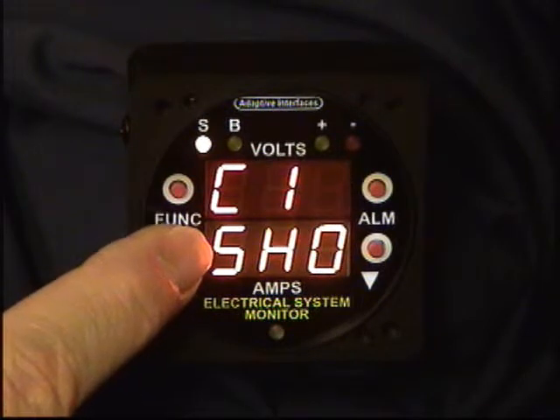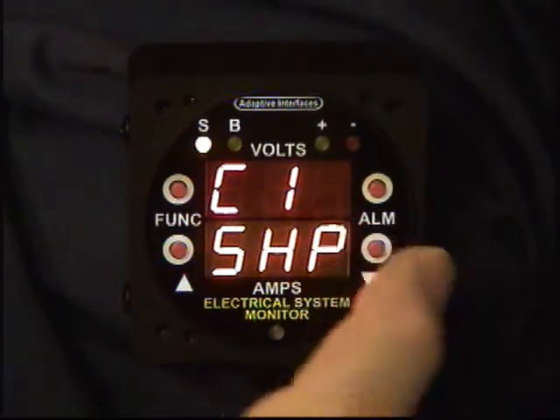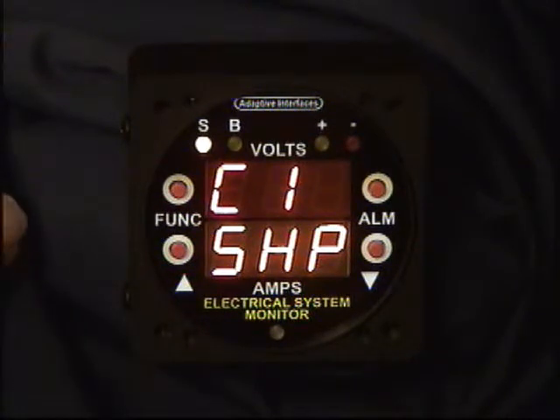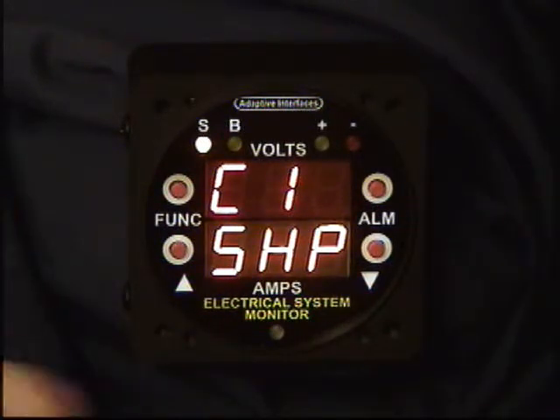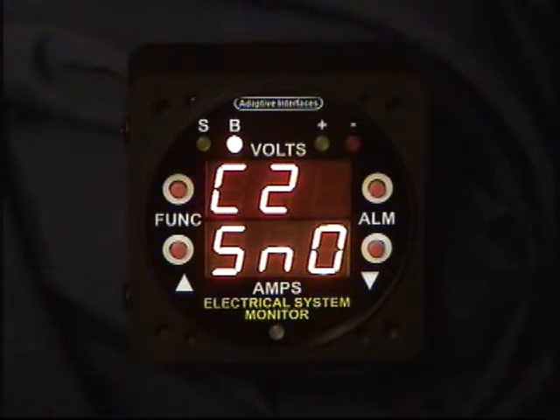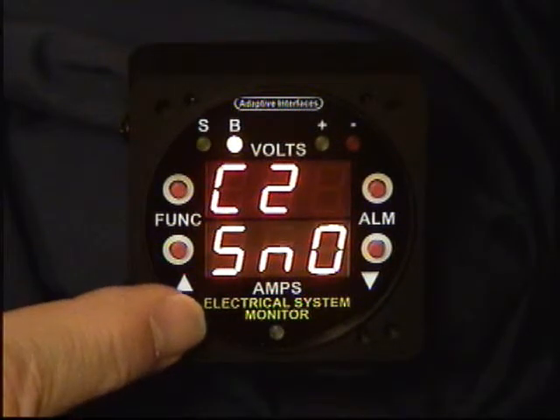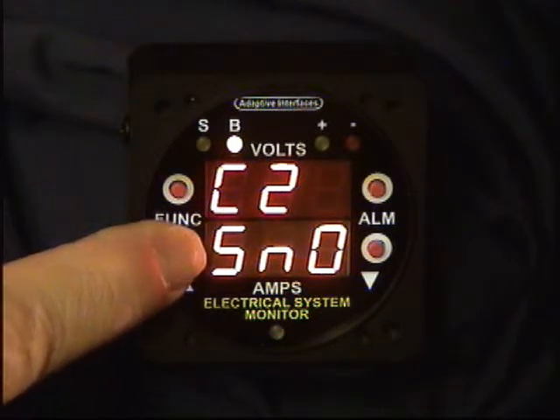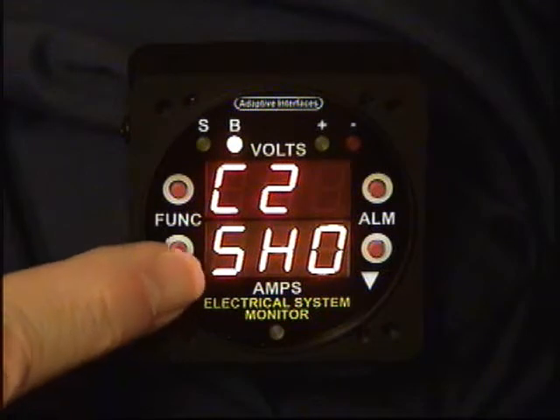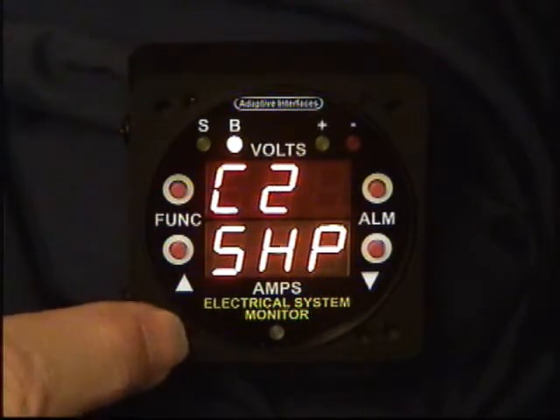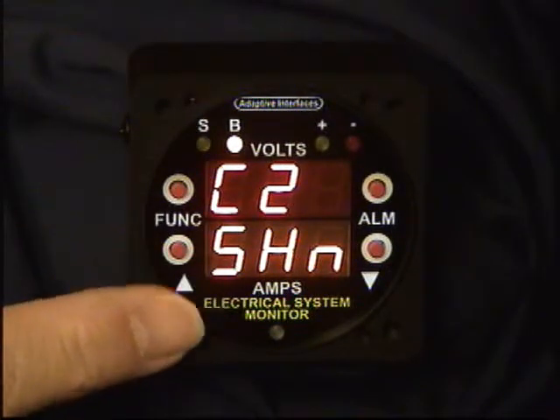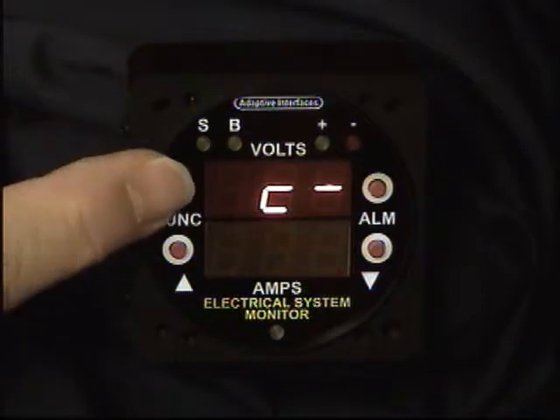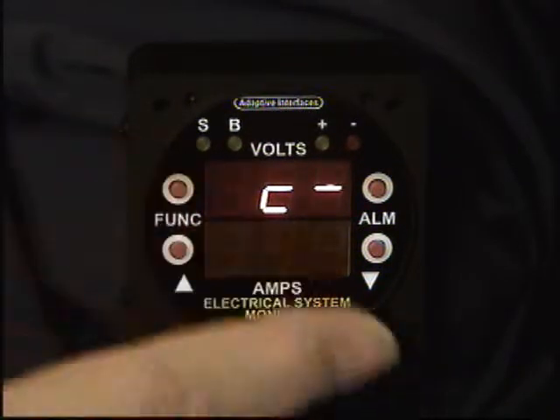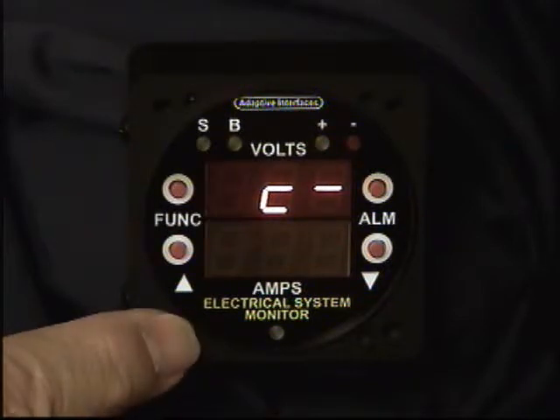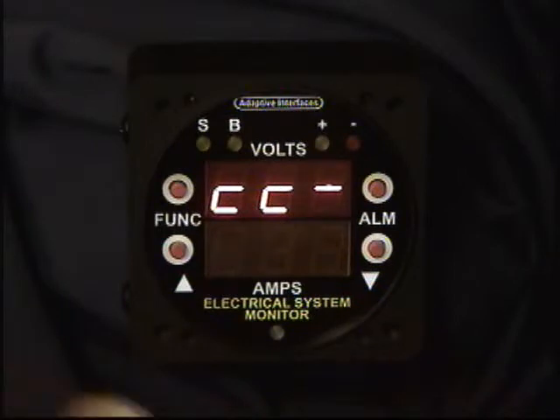And again, we can go through the different functions by hitting the up and down arrow. If you actually want to set that data point, you have to have a calibration instrument on the gauge and then use your alarm or enter button for that. And for current sensor 2, we have the same set of data points. The first data point is the 0 point for the Hall effect current sensor, the next is a 0 point for a shunt type sensor, a positive 50 millivolt point for the shunt, and a negative 50 millivolt point for the shunt. And the next two functions are a return one level function, which will bring you back to menu level 2 and those sets of functions, and a return to main, the main operating mode of the instrument.